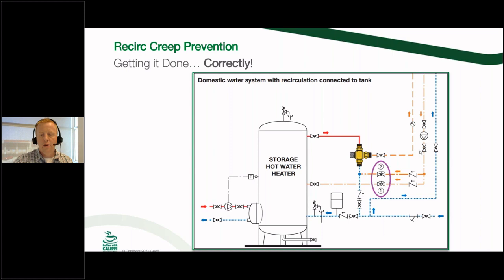And what you're going to see here is, instead of the recirc coming back and just tying in at the cold inlet of the mixing valve, the recirc comes back and ties in at the cold inlet, but it also goes right around and connects to that domestic hot water source. Now, if you don't have a tank tapping, you might end up coming right down here to the cold inlet of the mixing valve. But along with that splitting of the recirc, you're going to have two valves, and you'll see them circled here in purple.